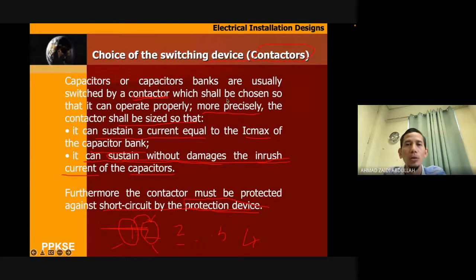And then the contactor. Capacitor banks are usually switched by a contactor. So normally we will install a contactor to switch on the capacitor, which shall be chosen so that it operates properly. Precisely, the contactor shall be sized so it can sustain the current equal to the IC max, and it can sustain the inrush current without damage. So that's the function of the contactor.